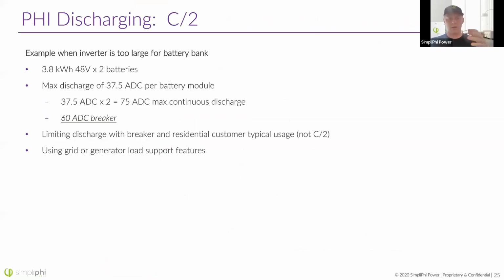So let's talk about one example here. We've got a 48 volt system with two 3.8 kilowatt hour batteries. So this brings us to a max discharge of 37.5 amps DC per battery module. That is a total of 75 amps DC for the battery bank as a whole. Now, you would usually want to use a 60 amp DC breaker on this type of system.